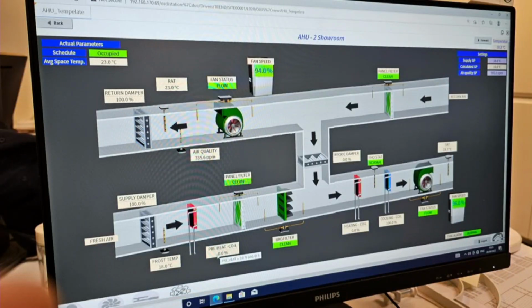This is another BMS download that we've done on the system. We said to the guys, okay, what speed are the fans running at? Well, they're on. That's what we were told. The fans are on. And we said, well, how fast are they running? Well, we don't have that feedback coming back to us. Why would we need that? So we said, well, surely you need to have more accurate detail coming through to you to understand what's going on with the system.